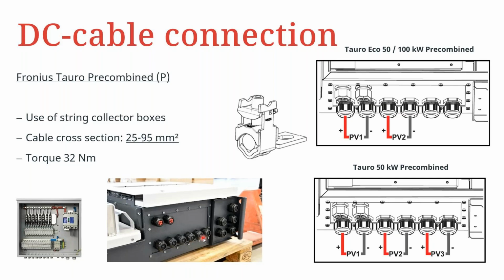So as you can see, provision has been made, and right inside the inverter on the DC side, we have what we call V clamps. These V clamps make it possible for you to have connected 25 to 95 square millimeter cable. Looking at the inputs for the Eco 50 and 100 kilowatt pre-combined versions, we have the respective inputs, PV1 and PV2. For the Tauro 50 kilowatts, we have 3 inputs for the MPPTs, that is PV1, PV2, and PV3.